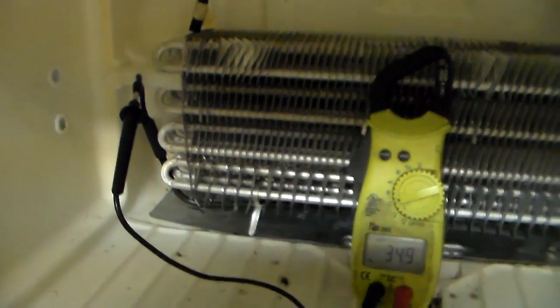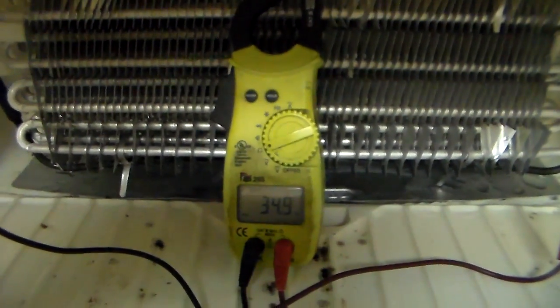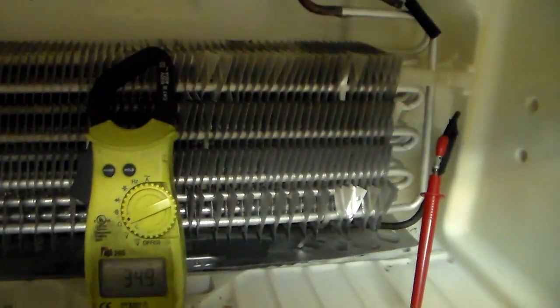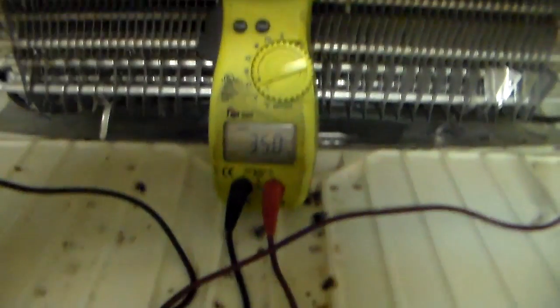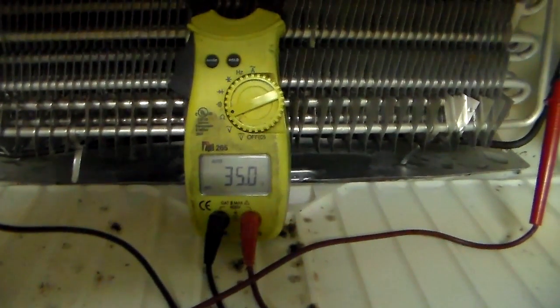So what I've done is my meter is set on ohms. One side of the heater, other side of the heater, about 35 ohms. The heater's good. So now we're going to move on from here.